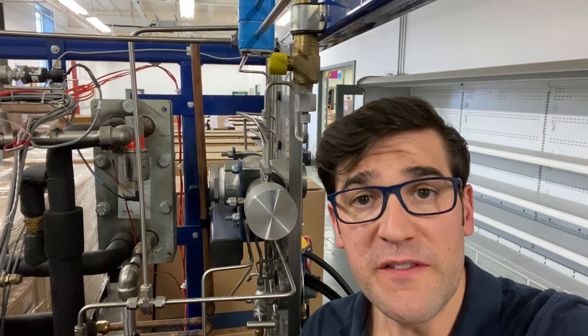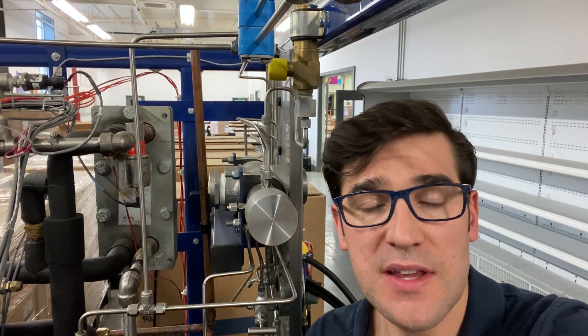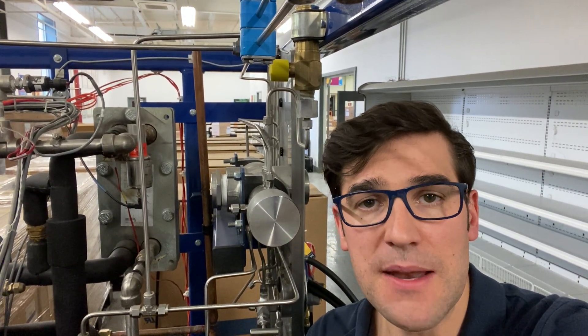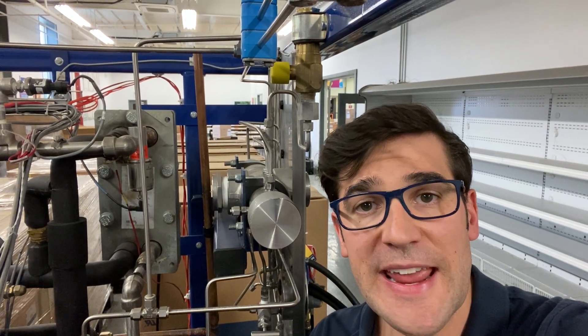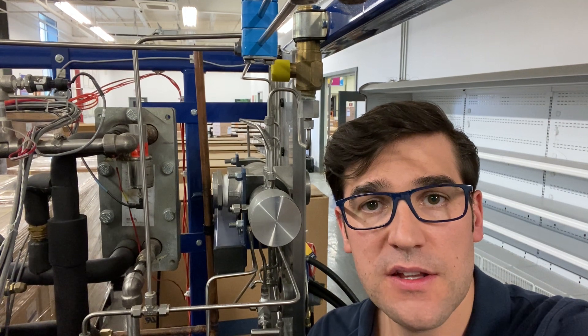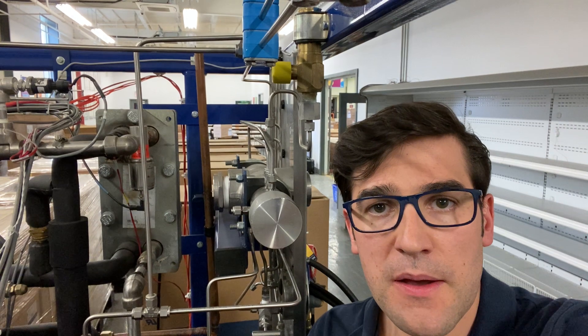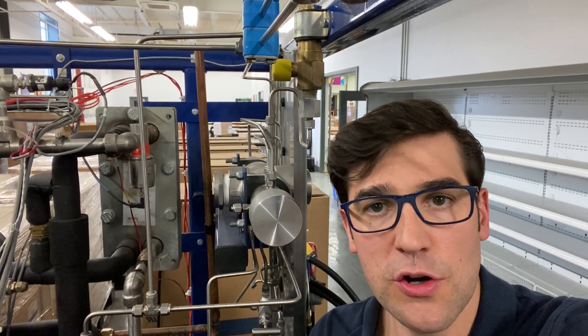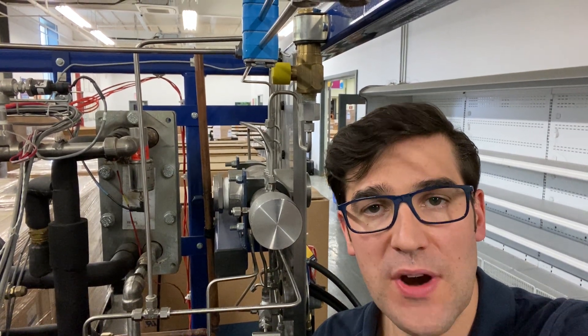I've talked about in a previous post why it's important to maintain superheat — check that out, it's in the description. It's very important to manage that because if you start going below 10K or 18 degrees Fahrenheit superheat — I usually tell everyone 20 degrees, it's easier in Fahrenheit — when you start going below that, you're going to start causing bearing wear in the compressor.